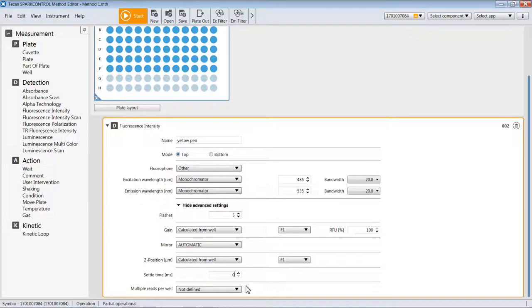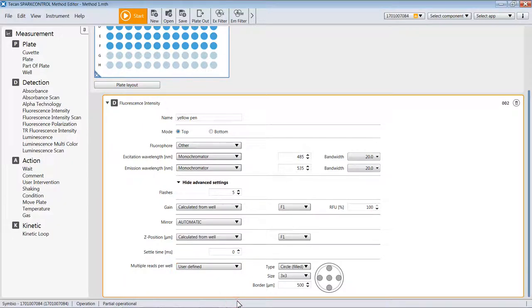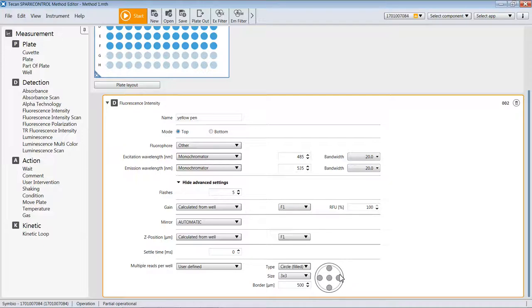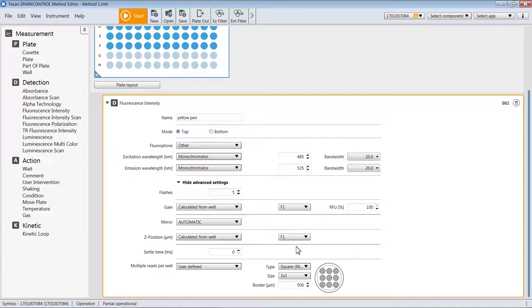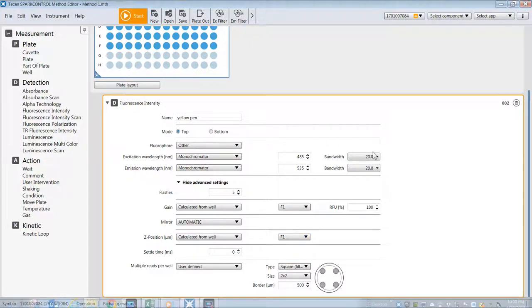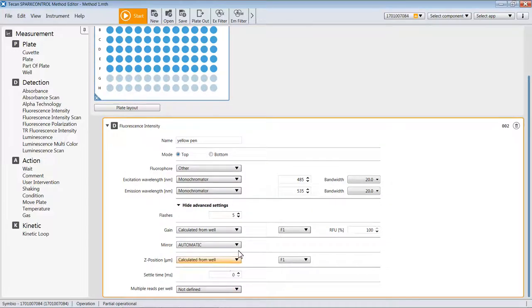There's a more advanced feature within the software called multiple reads per well. It's going to take additional readings at different physical points inside the well, based on the number of flashes you've given it. If I've got five here, it would flash five at different points and give me individual fluorescent intensity values for these five points, plus an average of those and a standard deviation for them. You can get pretty carried away with different types of patterns and densities here, getting some averages from the wells if there are features in the well that you feel must be measured independently. For this example, we'll turn off the multiple reads per well and just use the center default read of five flashes per well in the center of each well.